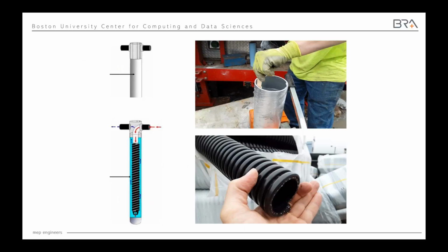All right, so how did we tackle geothermal on a tight urban site with such a tall building? Well, normal geothermal systems go down about 500 or 600 feet. We went down 1,500 feet, so 3 times as deep, to put in more heat exchanger area, more borehole area to get more capacity out of that ground.